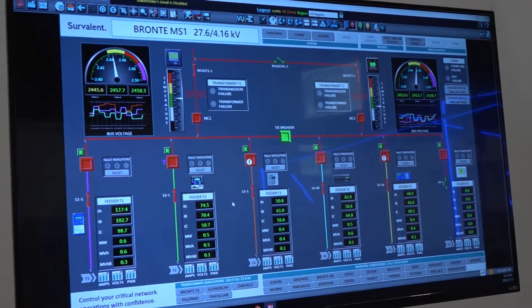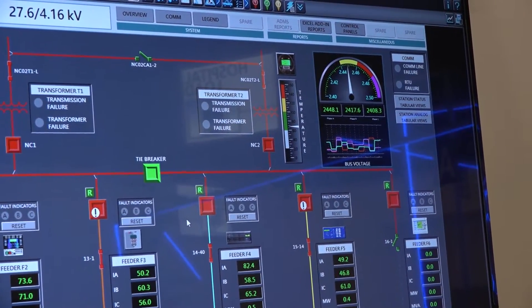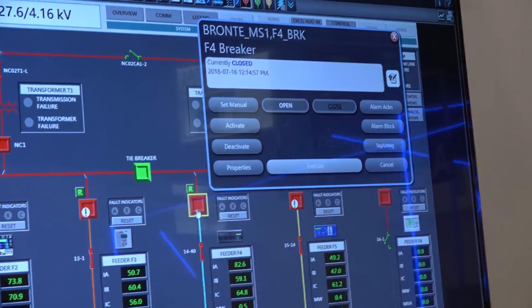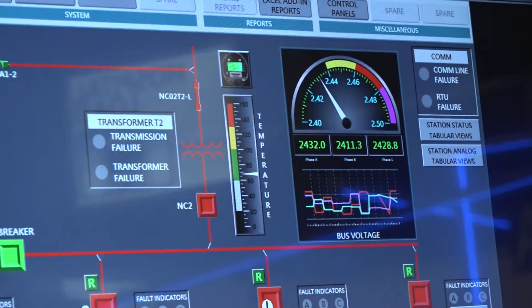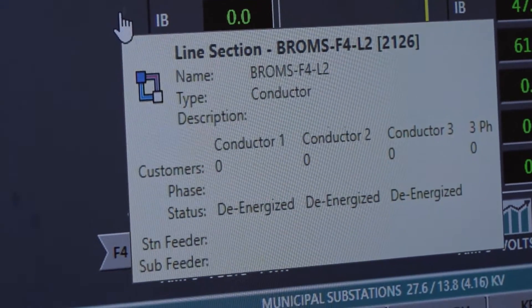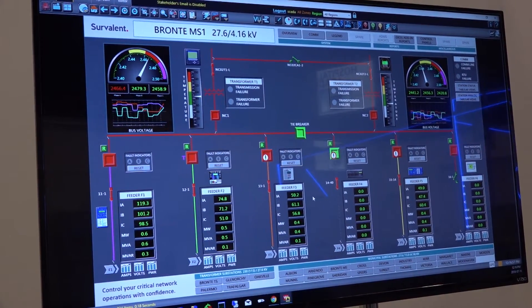Another key component for operators and dispatchers is being able to see everything inside the substation. They can draw single line diagrams inside SmartView using the editor tool. Inside the substation, whenever you issue a control — whether it's telemetry or a manually set point — you can click on any of the breakers or devices and issue an open command. Once you execute it, you'll see the topology processor update your line sections. You can hover over a line section to see exactly what the station and substation feeder is for that particular line section.